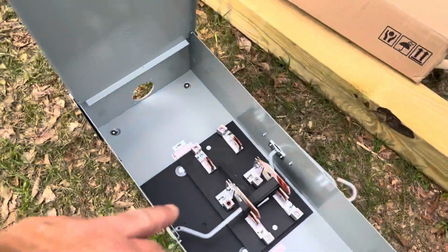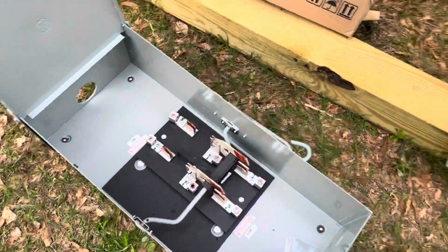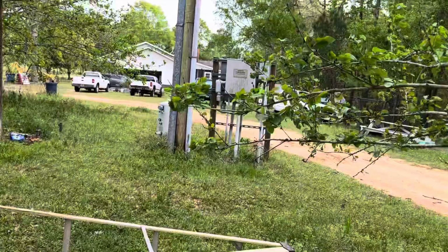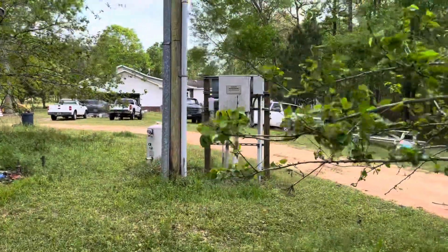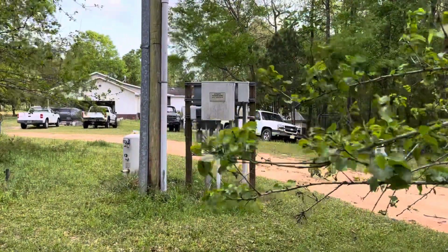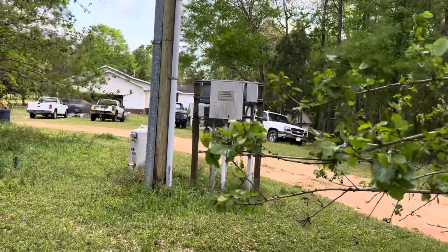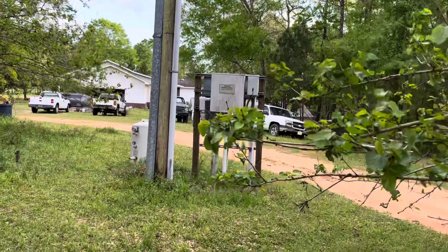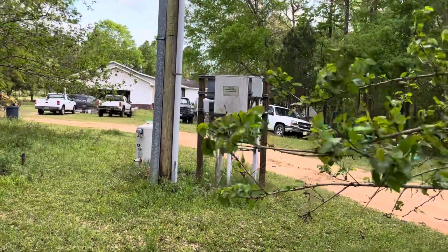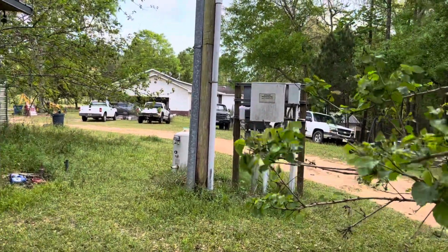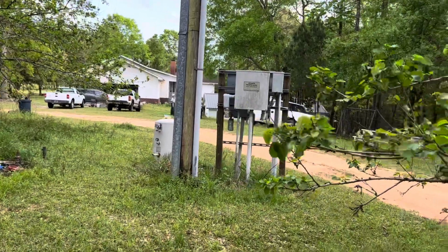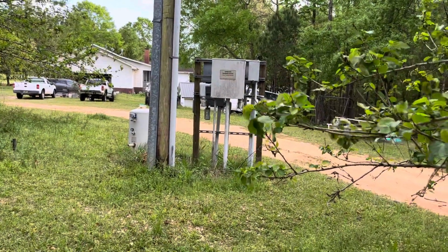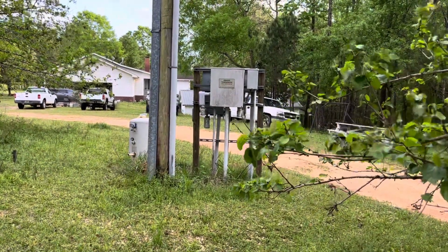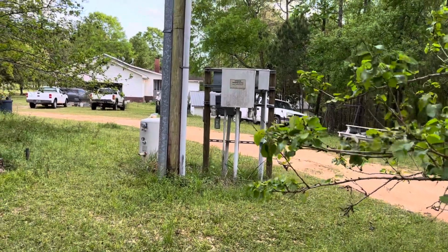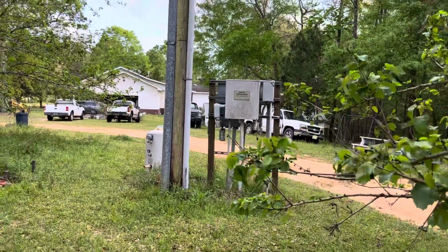And then from the load side, which is the center lugs, I'll feed back over to the automatic transfer switch right there, which is getting power from my generator. So I'm intercepting the power between my meter and my automatic transfer switch. And that automatic transfer switch is a service rated switch, so that's the reason I go straight from the meter to the switch.